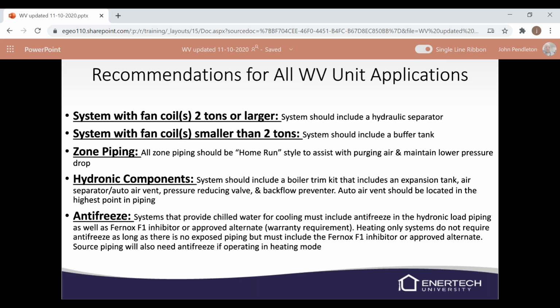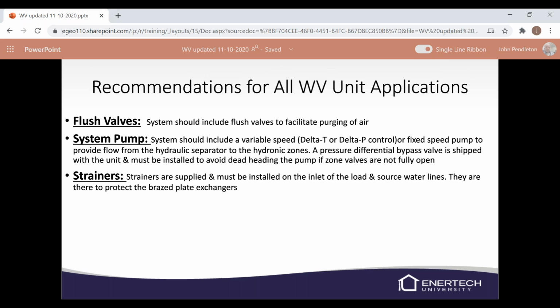Flush valves. If you've got a buffer tank or the hydraulic separator, you will need to add external flush blocks to your zone piping. And it's also going to have an external pump. That could be variable speed, it could be a fixed speed, that's totally up to you. If you've got the hydraulic separator or the buffer tank installed for your zoning, make sure you're putting a bypass valve installed in that circuit as well.